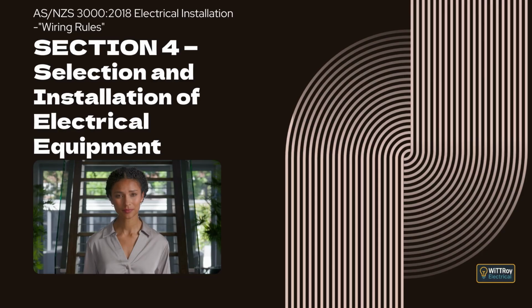Clause 4.13.1.3, Devices for starting and stopping. Devices used for starting and stopping motors must be located so they can be easily operated by the person responsible for the motor. A stopping device or isolating switch must be provided wherever danger is likely to occur due to moving parts.